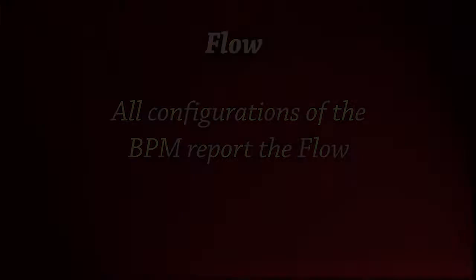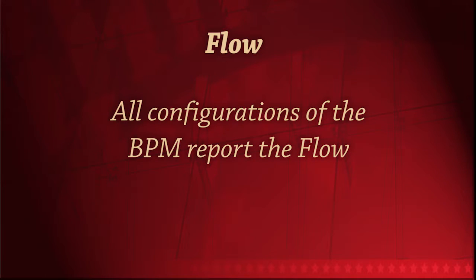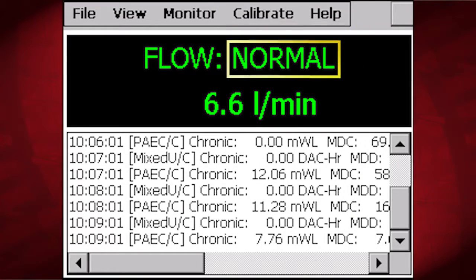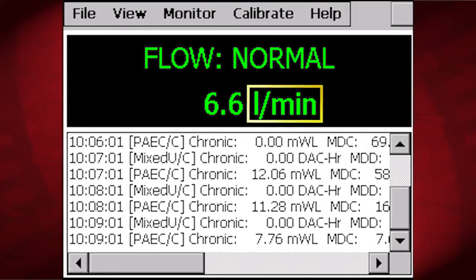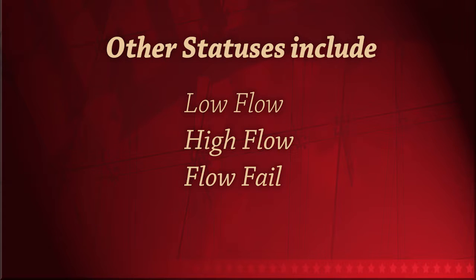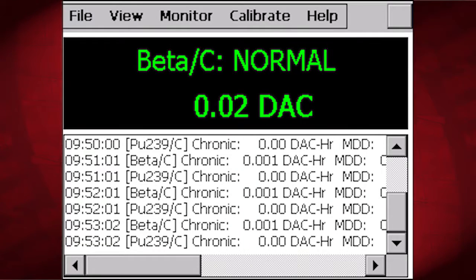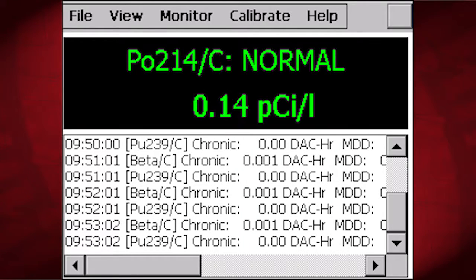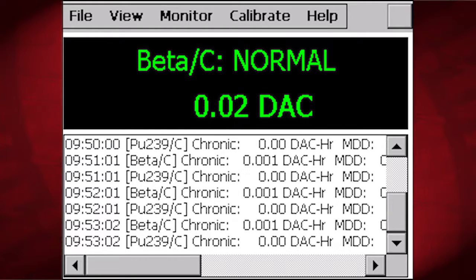for mixed uranium. All configurations of the BPM report the flow, whose status would be normal and units set to liters per minute. Other statuses include low flow, possibly indicating a loaded filter that needs to be changed, high flow, possibly indicating the lack of a filter, and flow fail, possibly indicating a malfunctioning pump, or, most commonly, the pump is just turned off. Go ahead and press the channel and units button to cycle through all the items being reported and their status. Stop when it is reporting the chronic beta again.